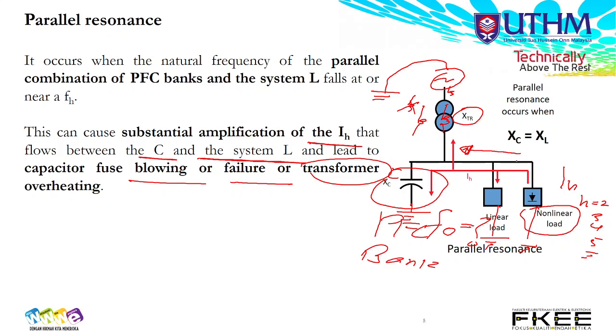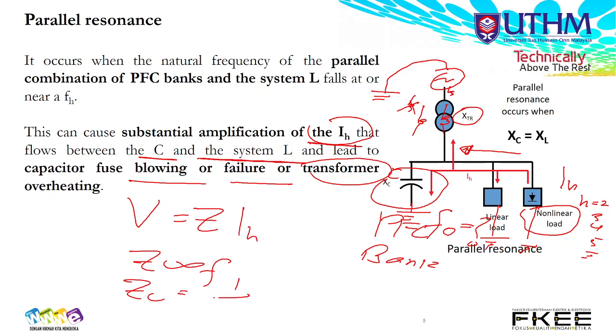Why? Because this harmonic current will produce voltage distortion, because V equals Z times I harmonic. When Z gets higher, Z depends on the frequency. Even ZC equals 1 over omega C, ZL equals omega L - all of this depends on frequency.